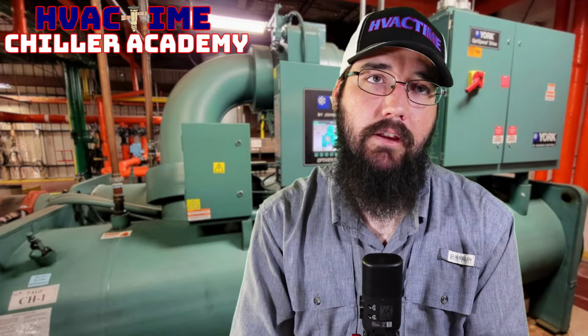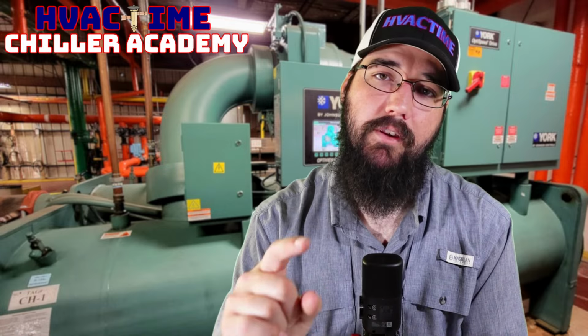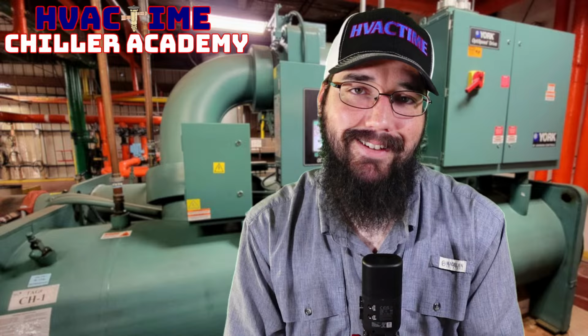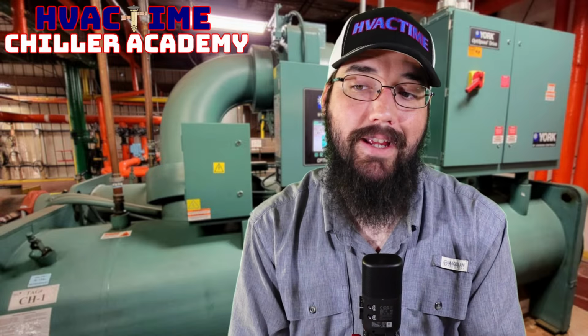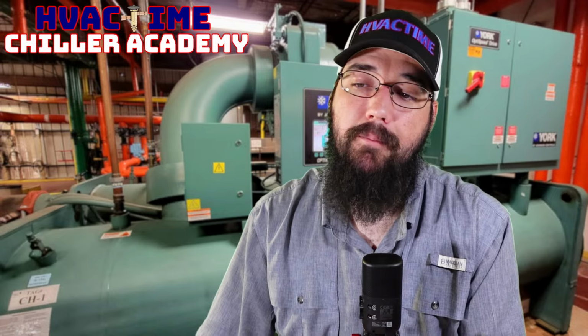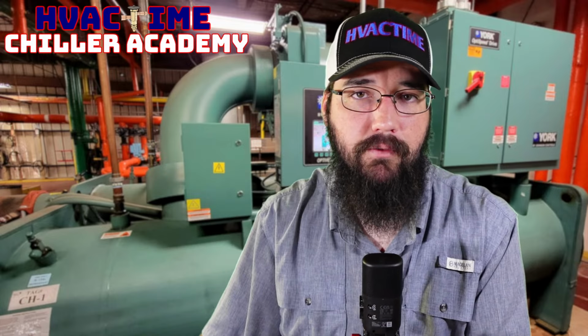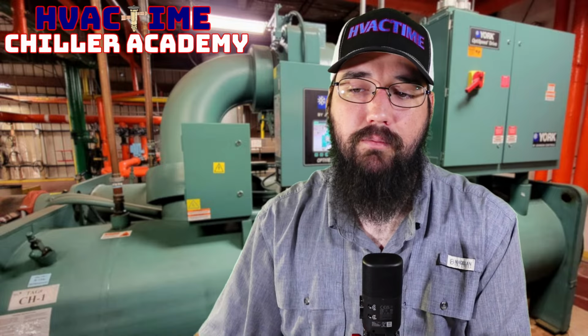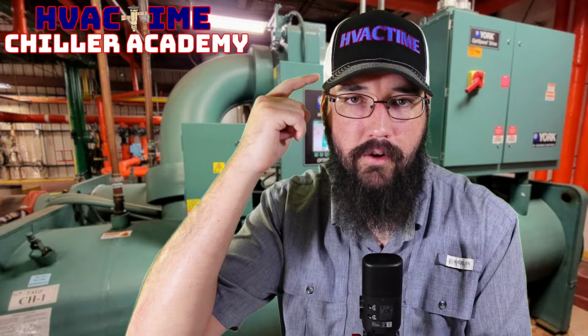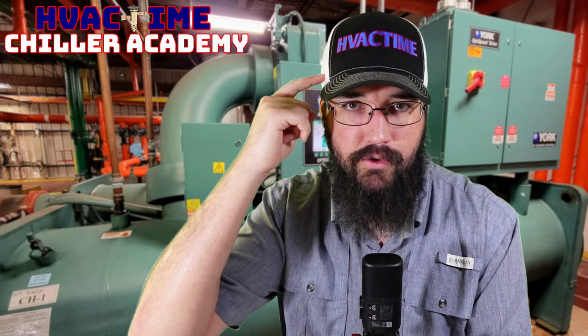Okay? One key thing to add that you typically don't learn with your current setup is approach. And by approach, I mean the difference between saturation temperature and leaving water temperature. That's a key one that we use in chillers that we don't really use elsewhere in the industry. It's not that it doesn't exist, we just don't use it. Those are numbers you can take, and they are useful if you just learn how to use them elsewhere. So yeah, those are some core things, right? If you can get your head around that, you will accelerate your ability to grab the rest of the machine very rapidly. Just build that mental bridge between water and air. And once you do that, so much of the rest of the machine starts to make sense much faster.